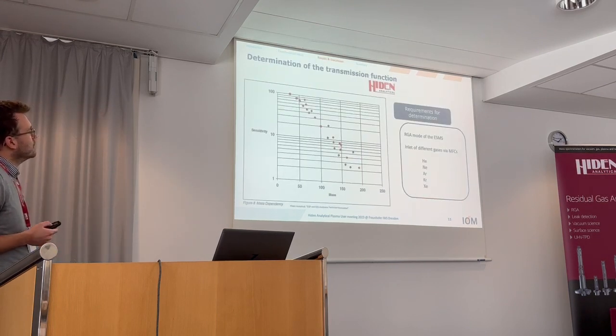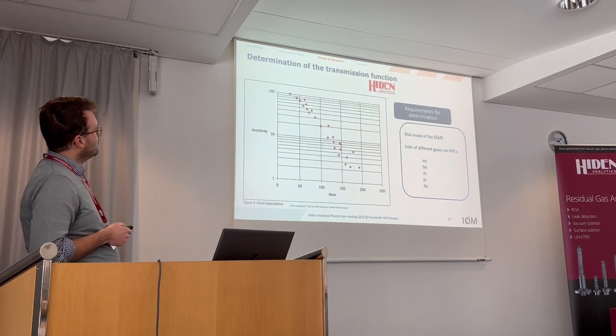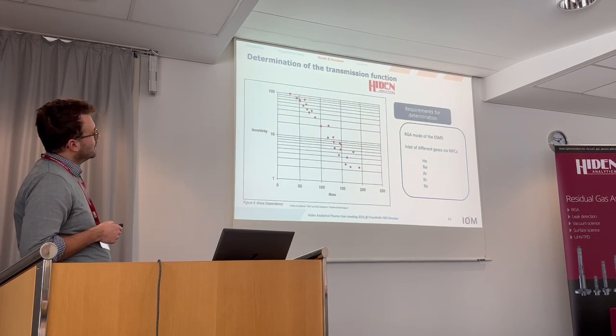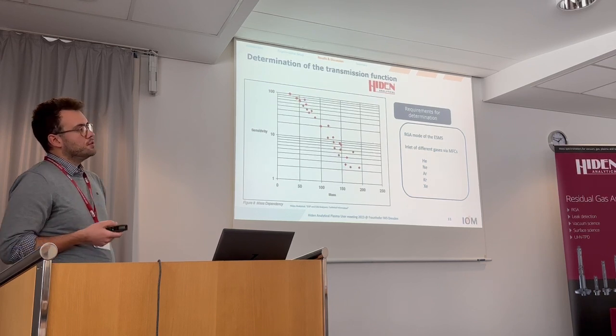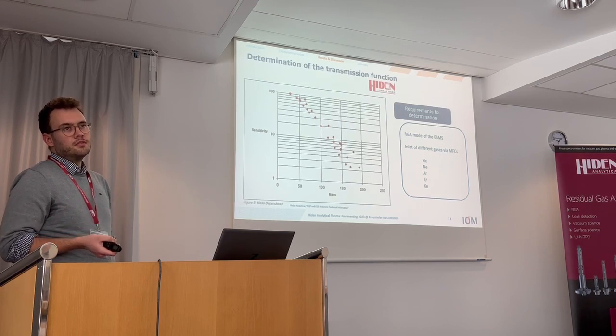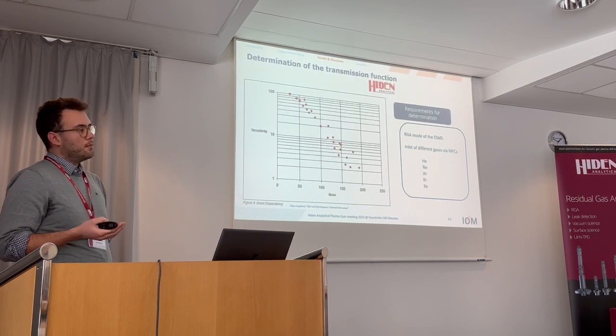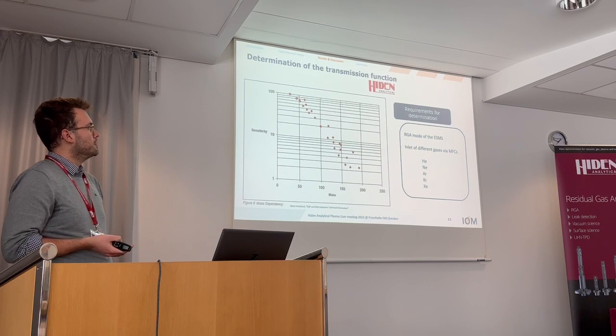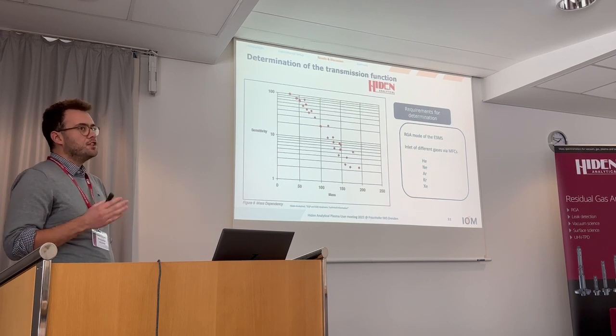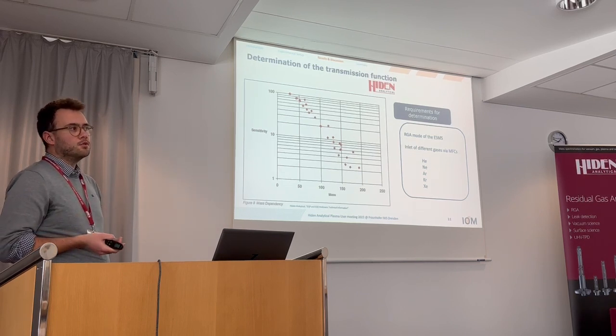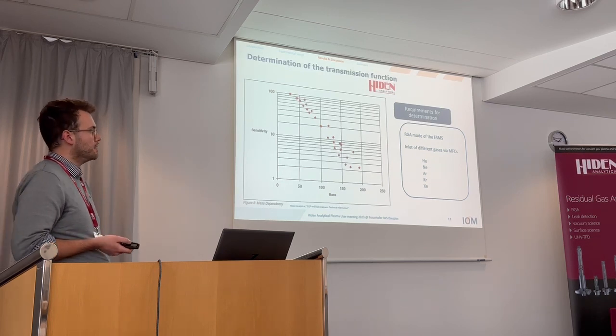Hiden also has some data available on the internet, as you can see here. There's the mass and the sensitivity of your EQP, and you can see that you have kind of an exponential decay of the sensitivity with mass. But we wanted to measure that for our EQP system to see what our mass-dependent transmission function looks like, because in several publications you find that this transmittance is very dependent on the tuning of your EQP.